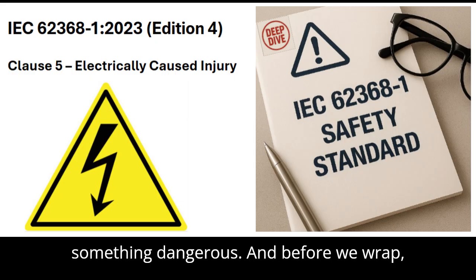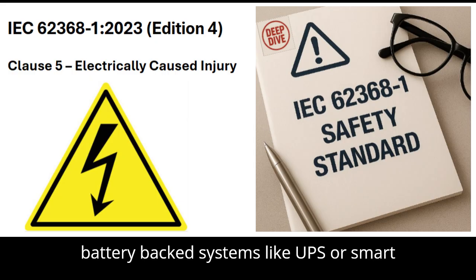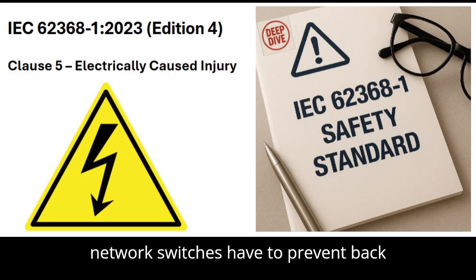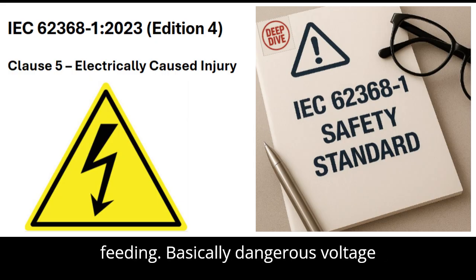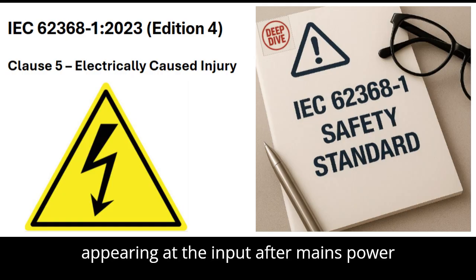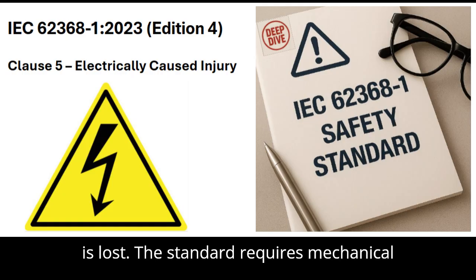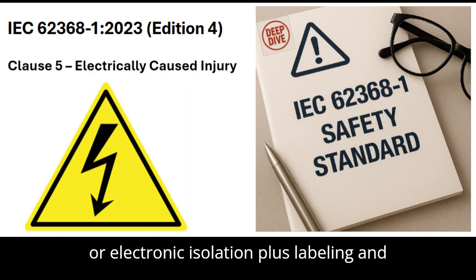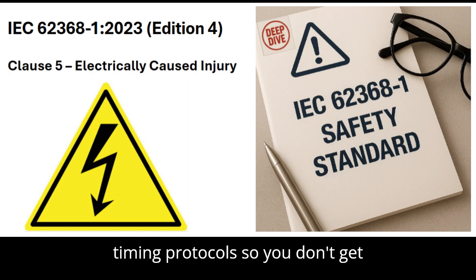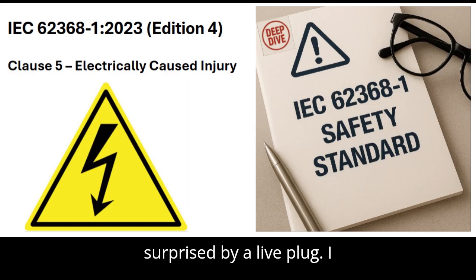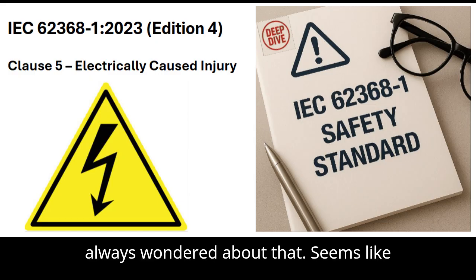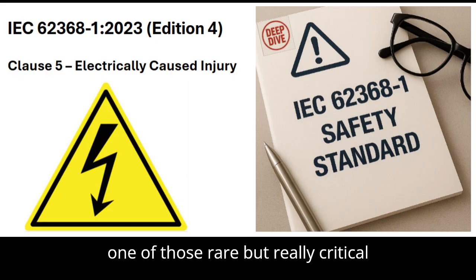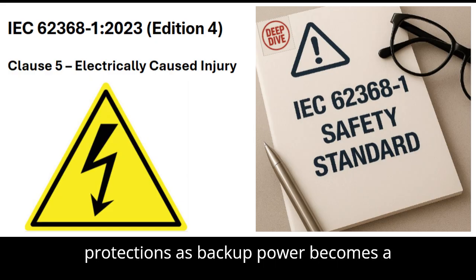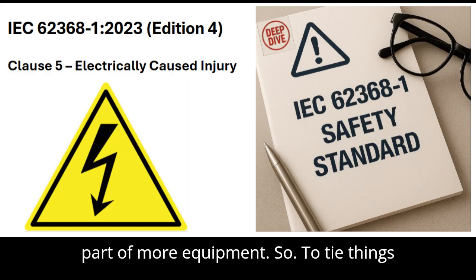And before we wrap, battery-backed systems like UPS or smart network switches have to prevent backfeeding, basically dangerous voltage appearing at the input after mains power is lost. The standard requires mechanical or electronic isolation, plus labeling and timing protocols, so you don't get surprised by a live plug. I always wondered about that. Seems like one of those rare but really critical protections as backup power becomes a part of more equipment.